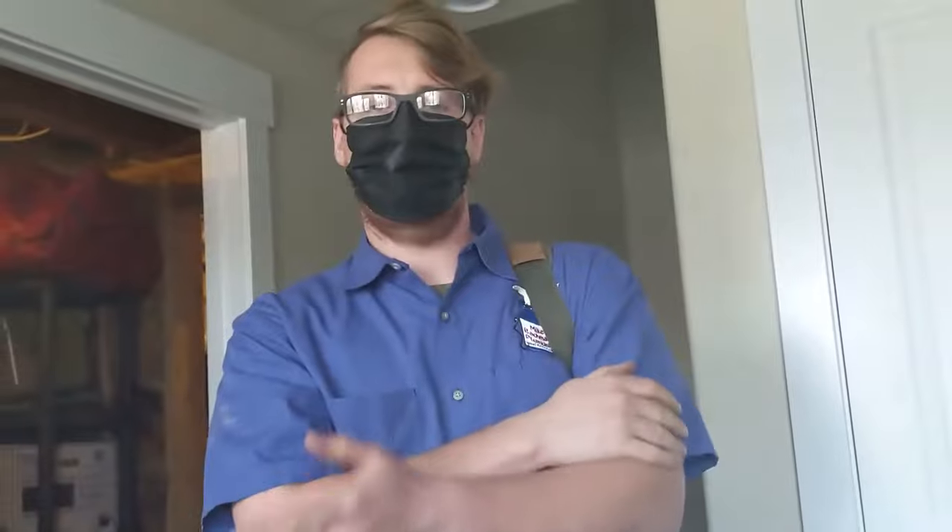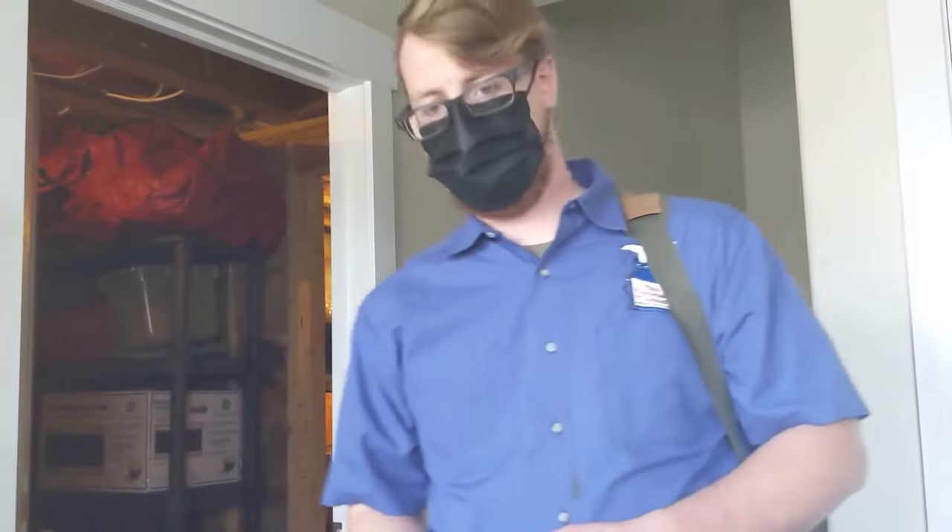If you're doing this every year, look for the color. If you turn it on one year and it comes out crystal clear, you're good — you don't need to flush it that year. If the next year you get sediment, white flakes or brown flakes filling your bucket, then you need to flush it: dump the bucket, do it again, repeat until it runs crystal clear. So you probably don't have to do this very often.